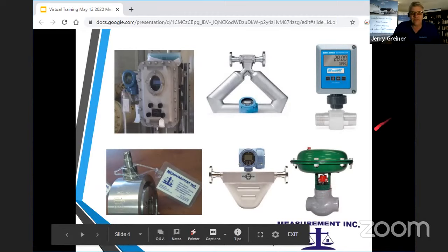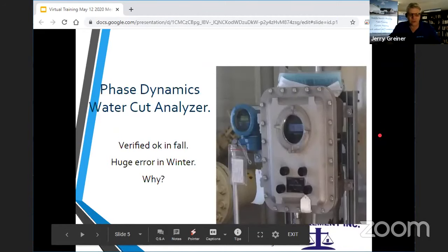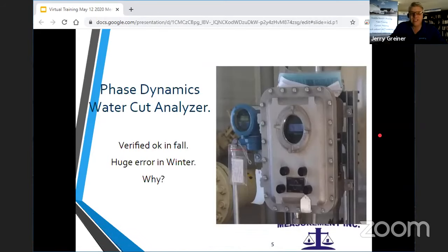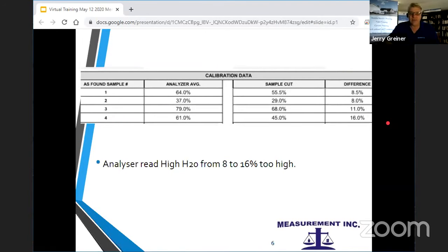So we'll start with our phase dynamics. One of these phase dynamics water cut analyzers verified just fine in the fall, but in the winter there was a huge error. And we kind of wondered why. The way we do these calibrations is we basically take samples. On this one, we did 4 different samples. You see what the analyzer is reading. Well, you take your sample, you heat it, you spin it out, you get a sample cut, and you see what the difference is. Normally, these are a fairly accurate analyzer. But on this particular one, the analyzer read 64%. The sample cut was 55%. And so it was reading about 8% extra water.